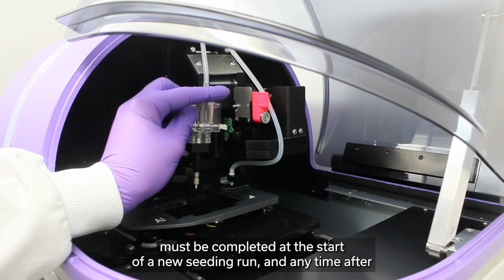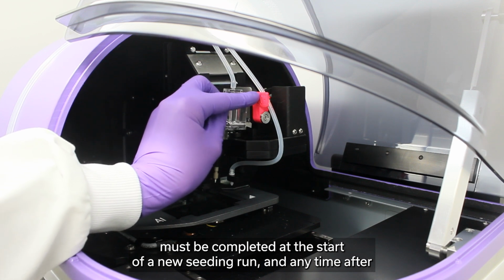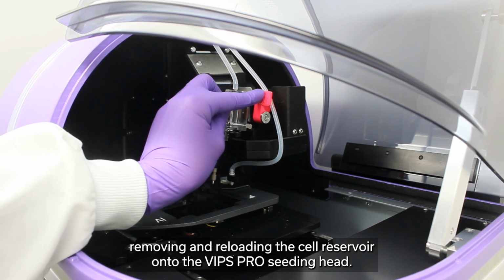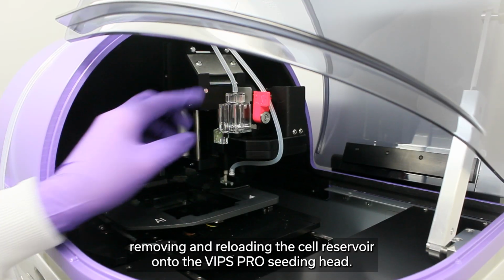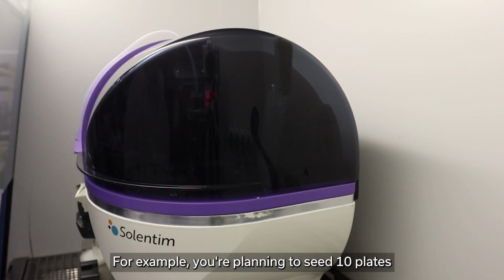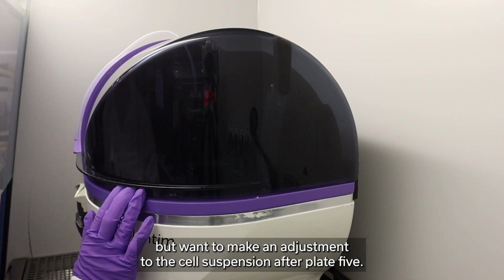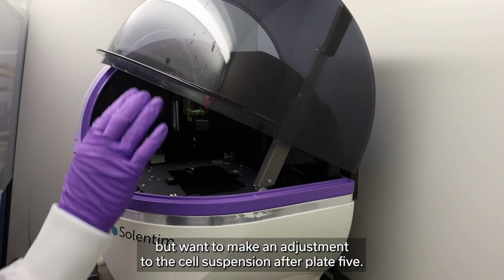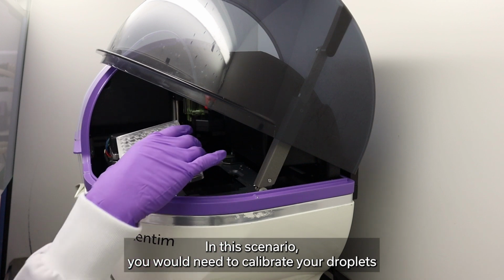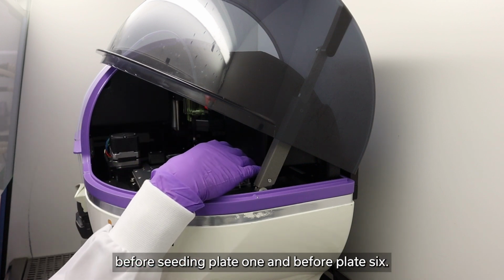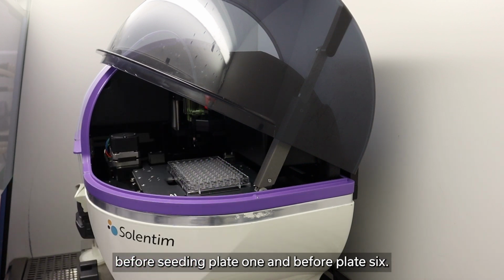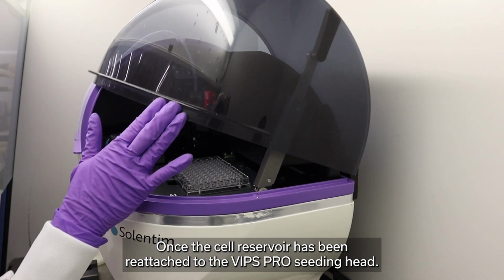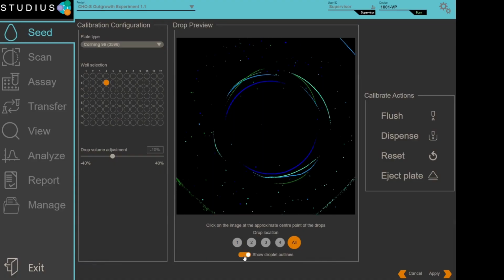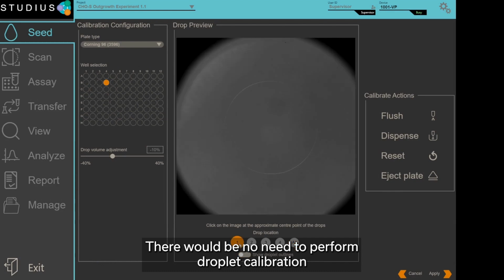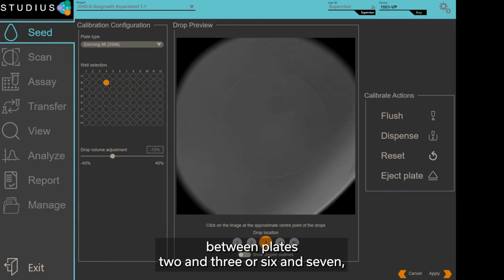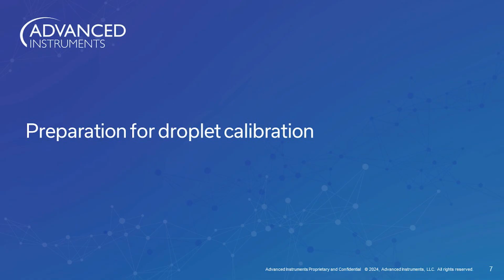Droplet calibration must be completed at the start of a new seeding run and any time after removing and reloading the cell reservoir onto the VIPS Pro seeding head. For example, you are planning to seed 10 plates but want to make an adjustment to the cell suspension after plate 5. In this scenario, you would need to calibrate your droplets before seeding plate 1 and before plate 6, once the cell reservoir has been reattached to the VIPS Pro seeding head. There would be no need to perform droplet calibration between plates 2 and 3 or 6 and 7, for example.